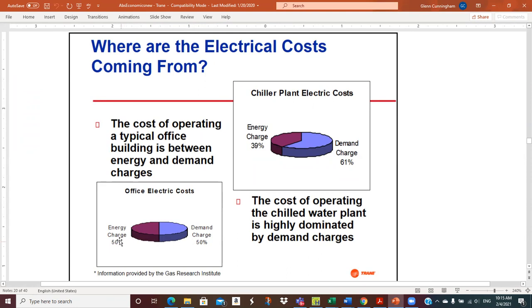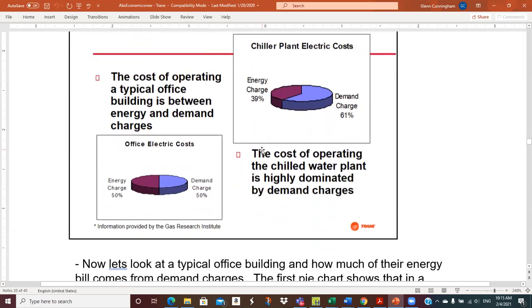50% of your electrical bill comes from the actual energy that you consume, and the other 50% comes from your demand charge based on your peak rate of using power. But if you look at just the chiller plant itself, analysis will show that typically the demand charge is about 61% of the total, and energy charge is only 39%. That's because it's typically a centrifugal chiller, and they've got big motors in them, and that really affects your demand charge. They operate heavily loaded just during a portion of the day, and then they back off during the rest. So during the rest of the day, the energy falls, but you've already set your demand peak.